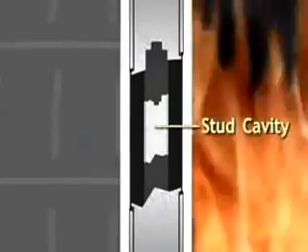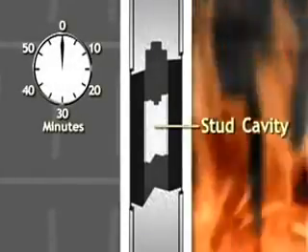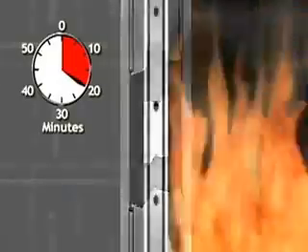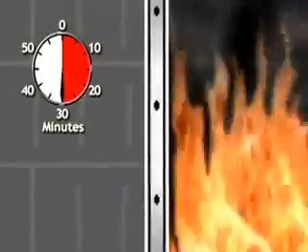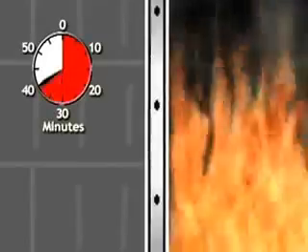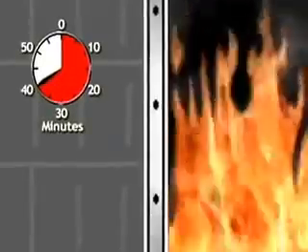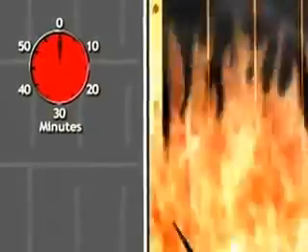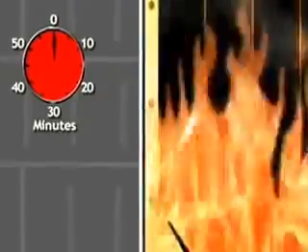Fire-rated gypsum board is only one part of a complete system composed of framing members, fasteners, fire tape, and mud. When erected properly, the stud cavity becomes an airspace that provides excellent thermal insulation, which is a key to the performance of these walls in a fire. The layer of gypsum board on the exposed or hot side of the wall is considered sacrificial and is not expected to survive the full hourly duration of a fire, provided that the last layer of the wallboard on the unexposed or cold side is fully intact at the end of the hourly duration.